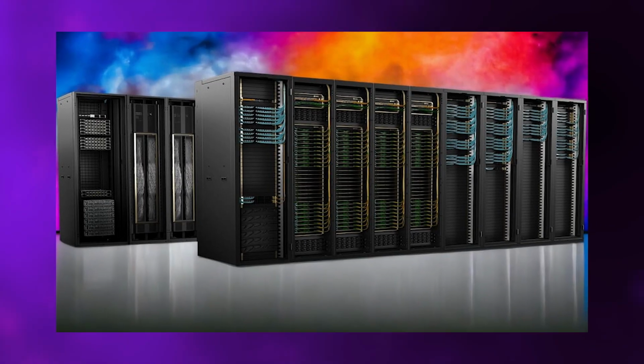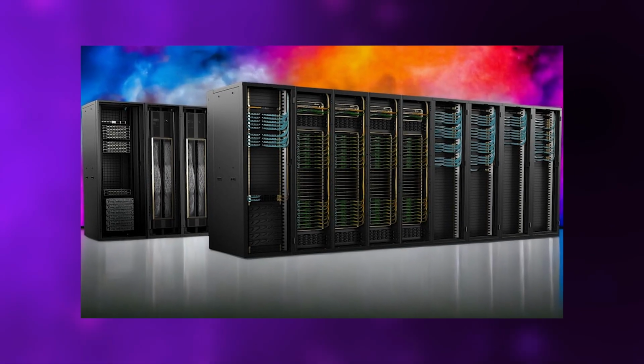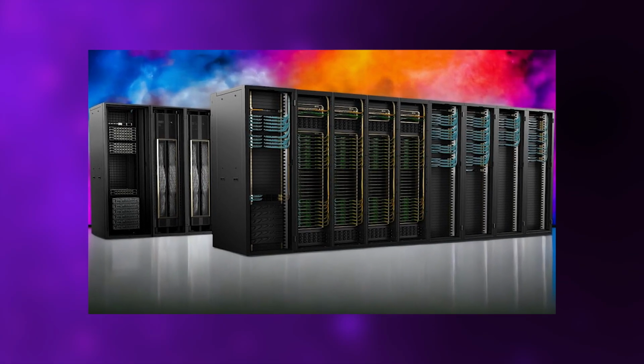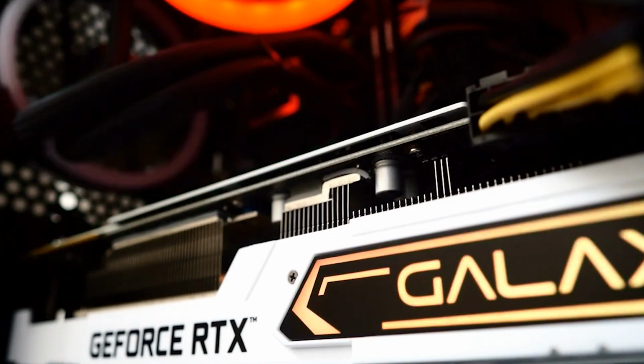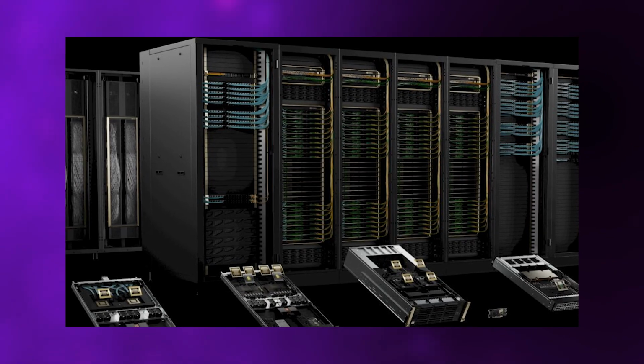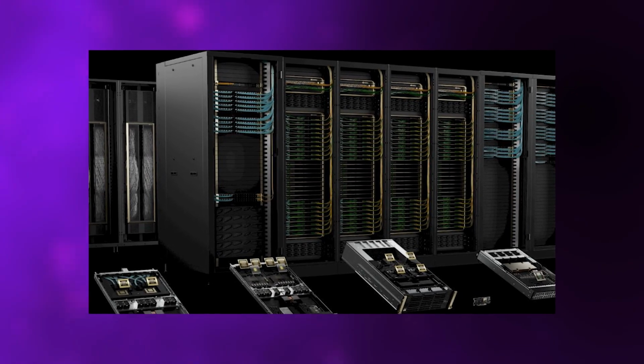NVIDIA's advancements actually make this worse through increased density. These aren't ordinary racks anymore, drawing 50 kilowatts. With new Blackwell chips, power draw jumps from 50 kilowatts to 130 kilowatts per rack. At this scale, each rack consumes as much electricity as a small neighborhood.